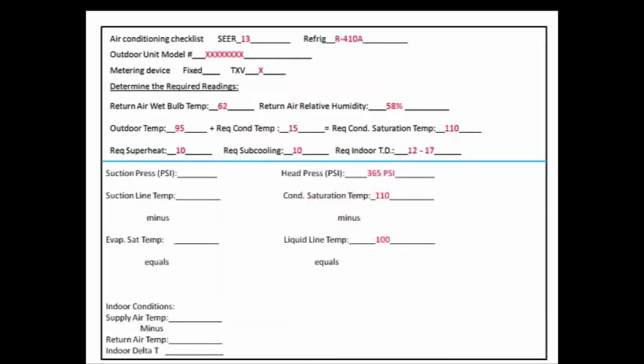So let's go back to our worksheet. Our head pressure is 365 psi. We convert that using a pressure temperature chart to a condenser saturation temperature of 110. From that we subtract 100, which was the actual line temperature of the refrigerant, and that equals 10 degrees of subcooling.